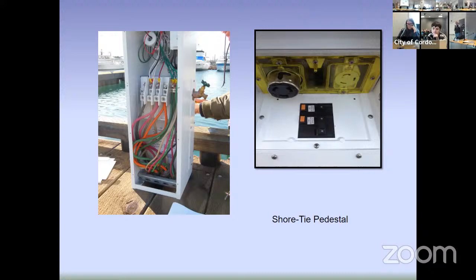Now, he was talking about the two receptacles in the pedestals. The two that we have going in, or in some cases we have three, but the predominance of them have the 30-amp, 120-volt receptacle for shore power. A lot of the boats, that's all they use. The larger stalls have the 50-amp, 208-volt receptacles, and those are also set to trip at 30 milliamps. What Mike Holt was talking about was a 20-amp receptacle that we don't have in our pedestals. Those are for maintenance purposes, not for shore power, and those are set for 5 milliamps, but we don't have those for the boats. The harbor might have some.